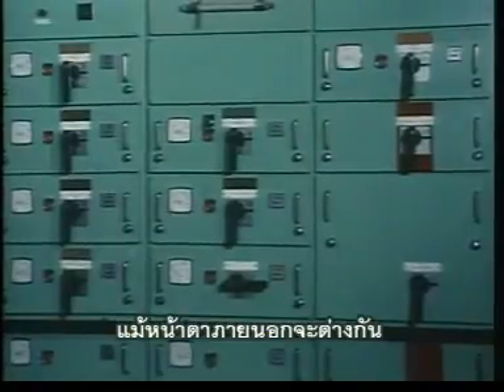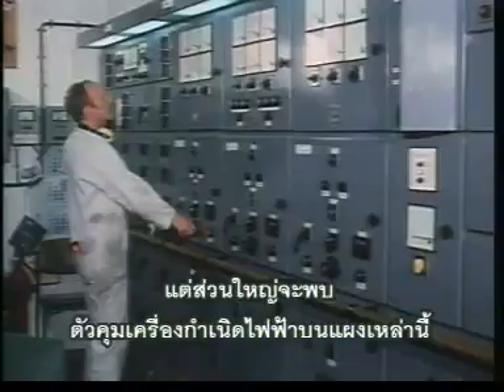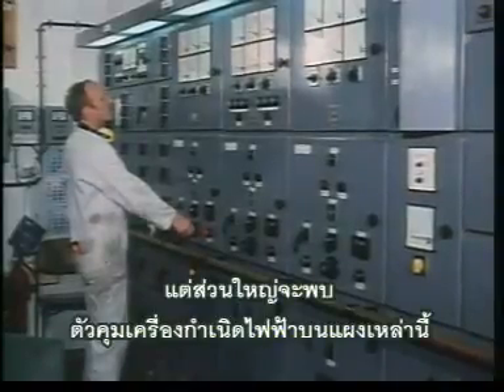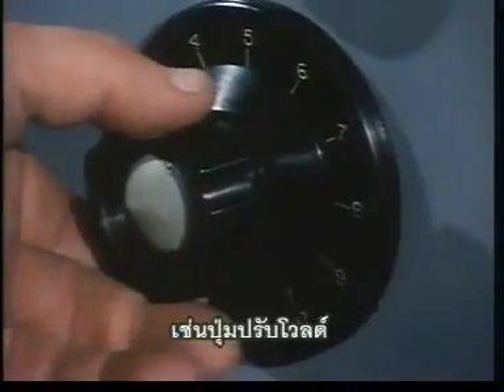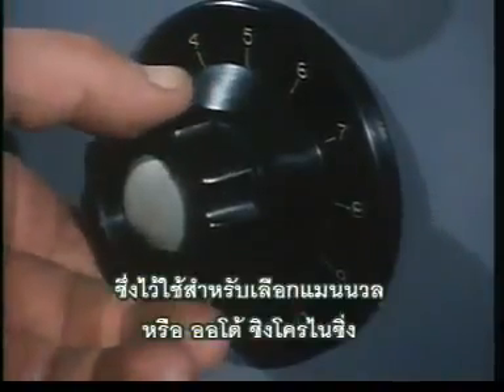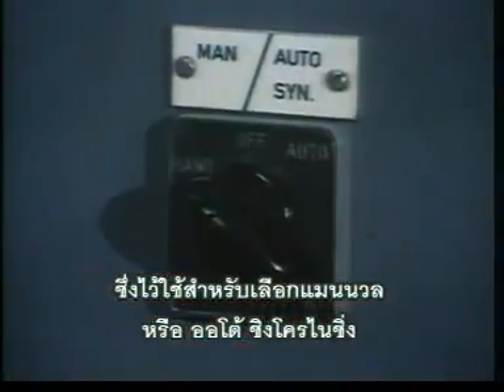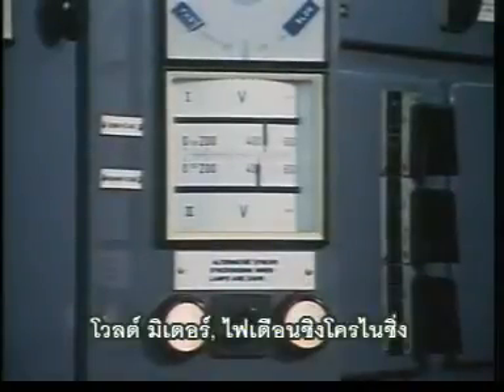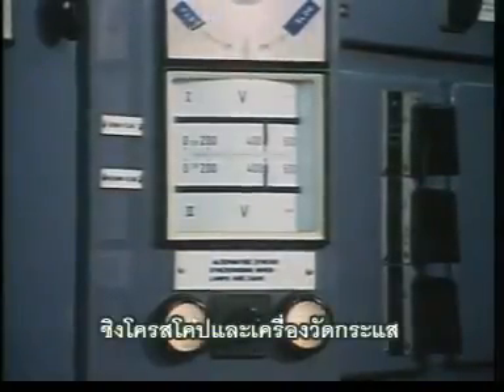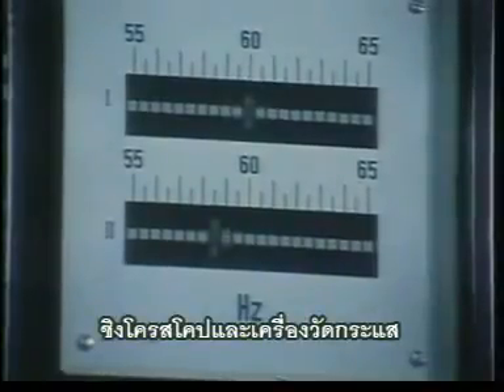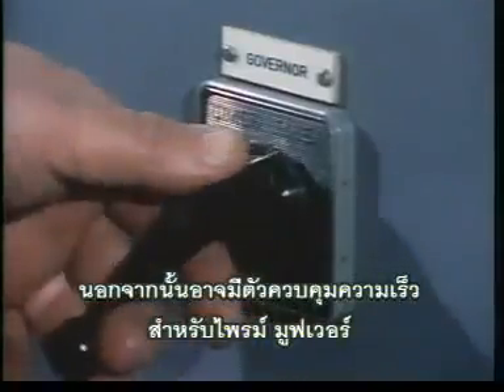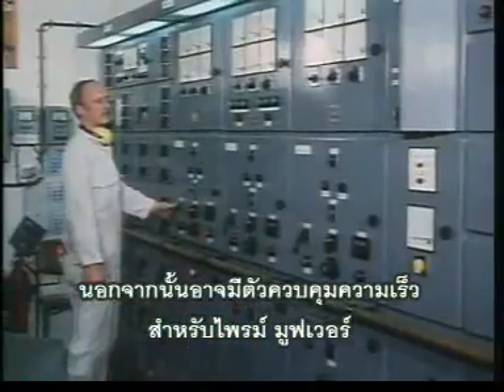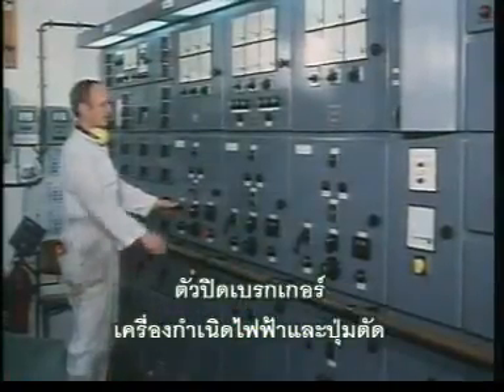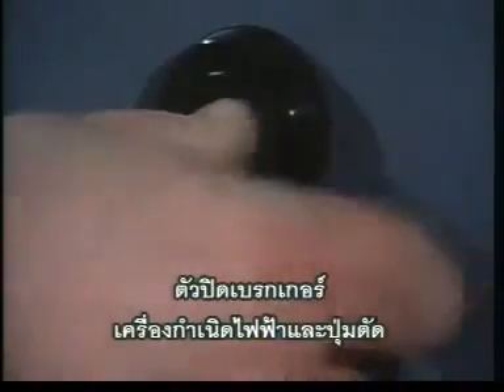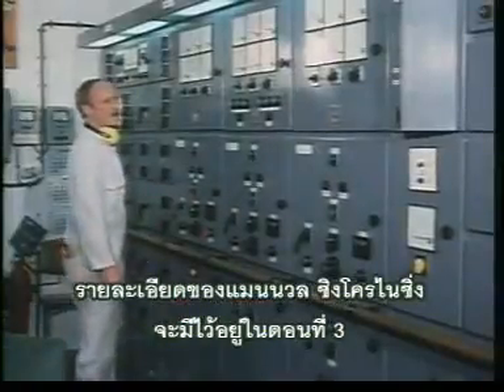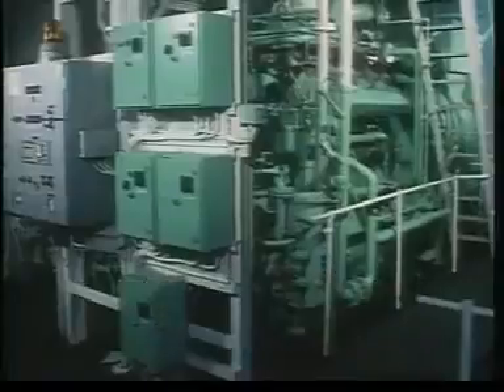Many configurations are in use, and in most cases the controls for synchronizing alternators will be found on these panels, such as a voltage regulator, selector switch for manual or auto synchronizing, voltmeters, synchronizing lamps, the synchroscope, and frequency indicators. In addition, there will be speed governor controls for the prime movers and alternator circuit breaker closing and trip buttons. A detailed description of manual synchronizing is given in Programme 3, dealing with alternators.